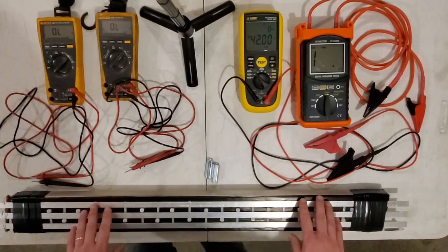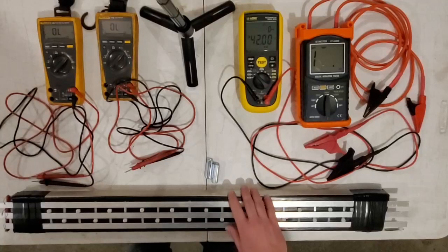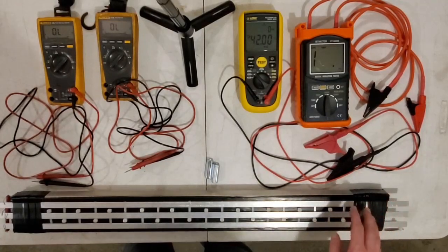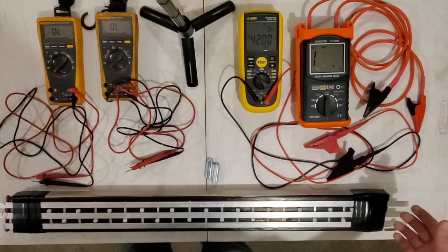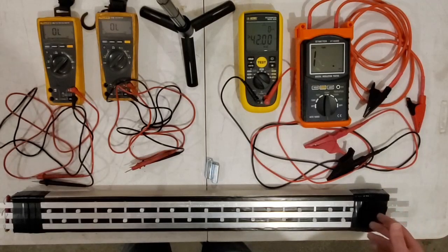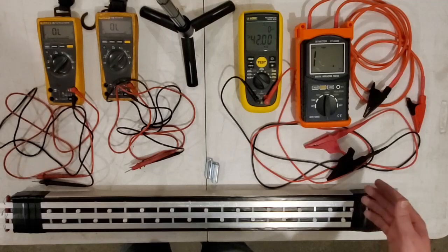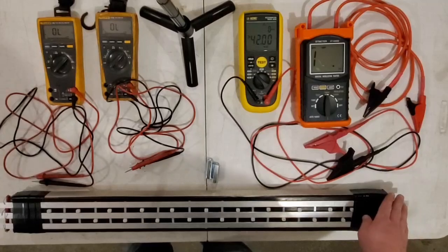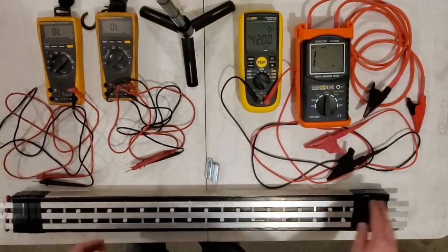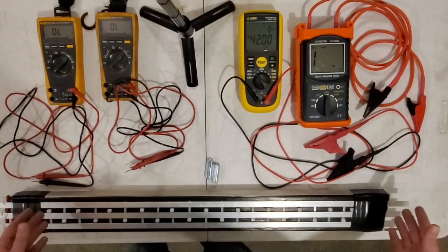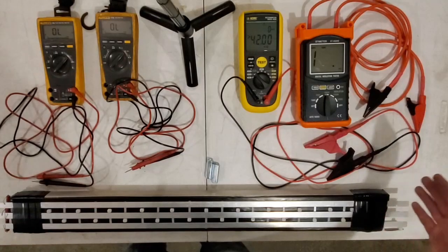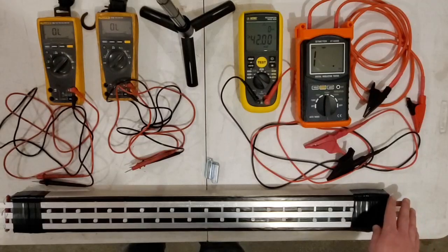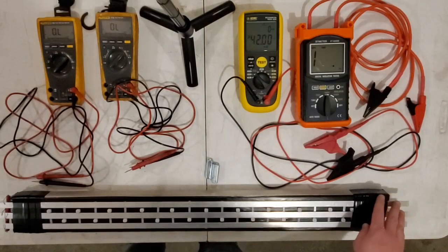If the insulation starts to fail, it starts going to the ground bars, it starts going to the people that are touching equipment, and that's not what we want. And then the other thing that we want to talk about is contact resistance. And what is contact resistance? Well, we want to make sure with contact resistance, or just resistance, that in order for the electricity and the charge to get from this end to this end, and from the source to the load, there's very, very low impedance to that flow, right? And with AC, it's impedance. With DC, it's resistance. But we want to make sure that it's very, very low.